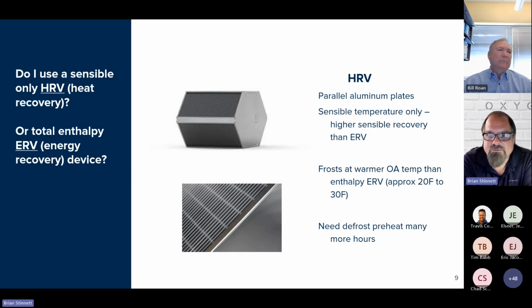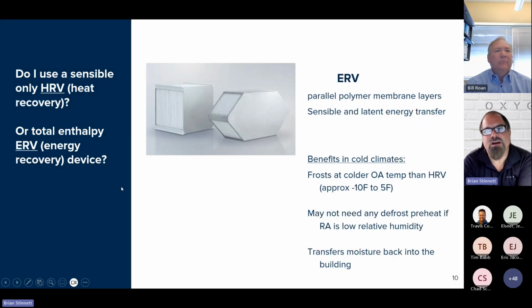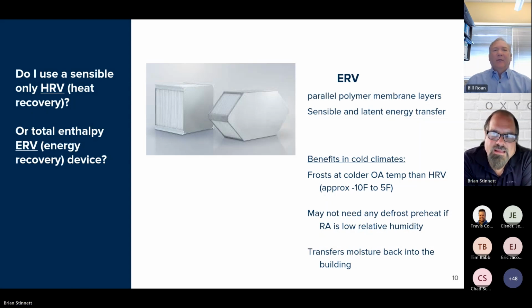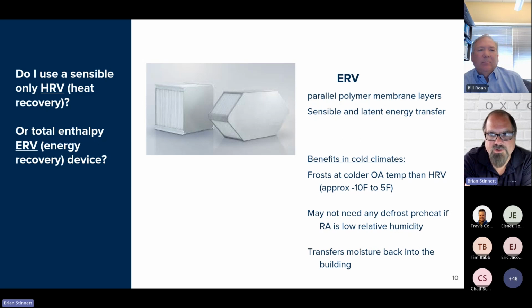So a lot of hours of running a preheater to make sure I don't frost. Conversely, if I look at an ERV, there's a couple of advantages for an ERV, which again is both sensible and latent transfer. A few advantages to using that ERV in a cold, dry climate like Denver. First one of which is the frost temperature is much lower than with that aluminum device.